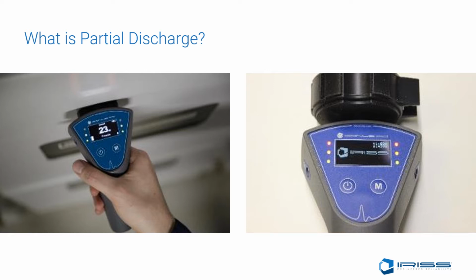The use of the comparison method can quickly identify any outliers that need further investigation. When using the comparison method, the inspector can not only compare similar equipment, but the same asset over time. In order to do this, the humidity, temperature, load, and voltage all need to be documented in addition to decibel values. PRPD results and sound waves at the time of testing will also be beneficial. Trending of the assets can also be established with enough historical data, and analysis of the PD cycles, decibels, and sound waves is critical. This information will allow the program to make an even more effective determination of why or when there may be an increase in the breakdown of the voltage. If these assets are left untested, the emissions will go undetected and will lead to a catastrophic failure.